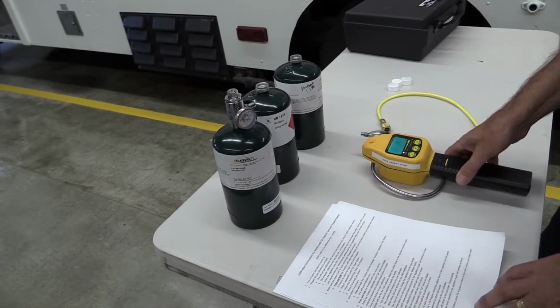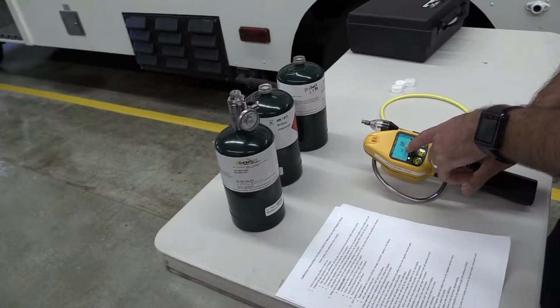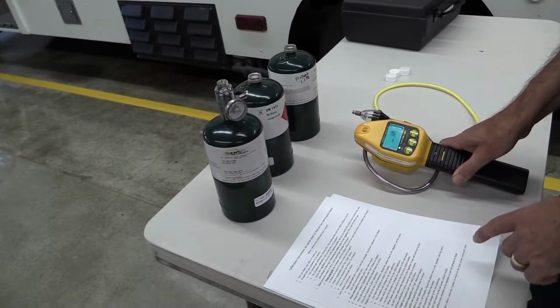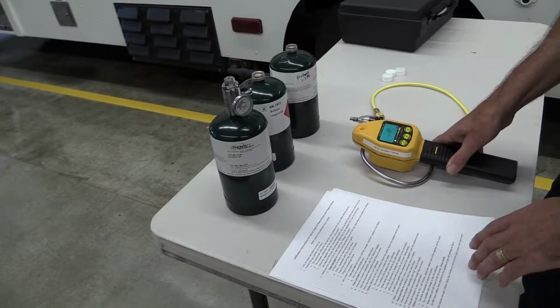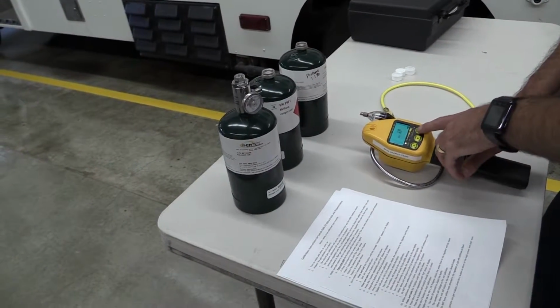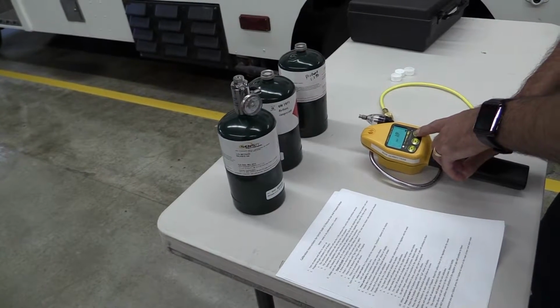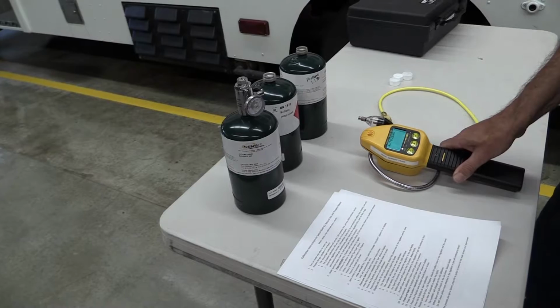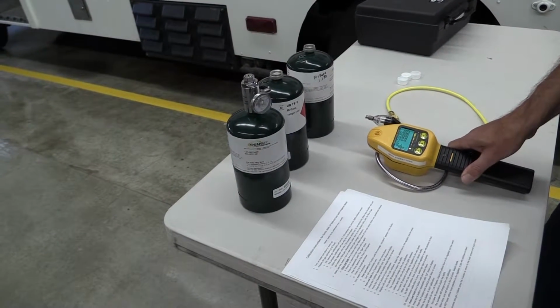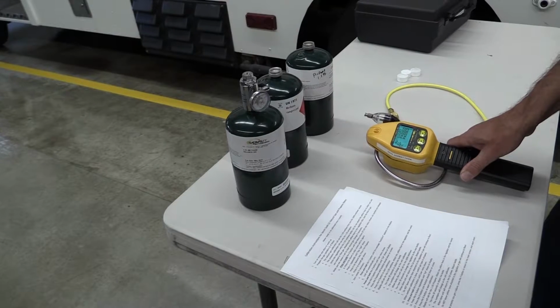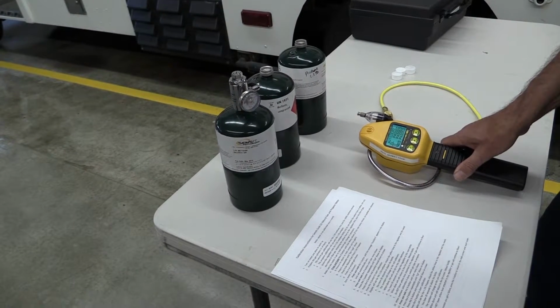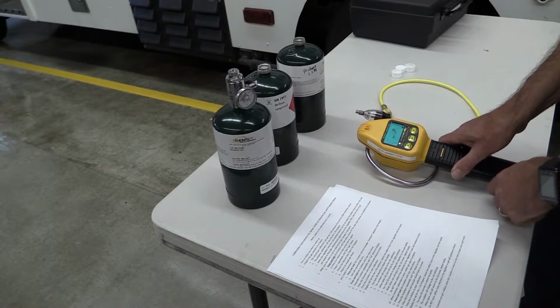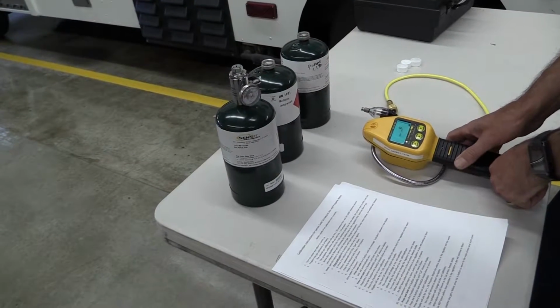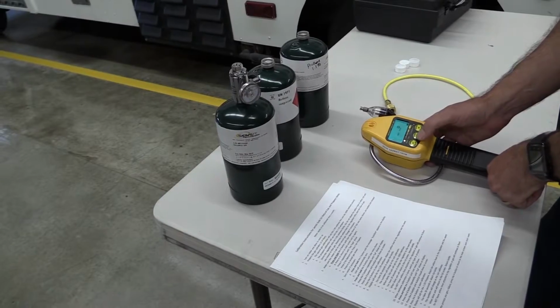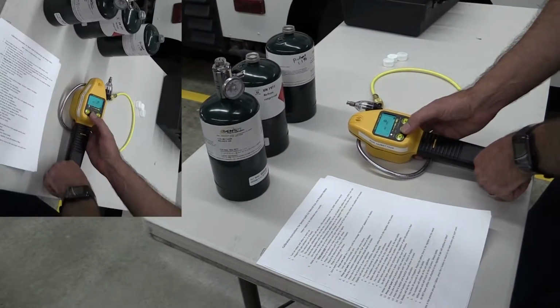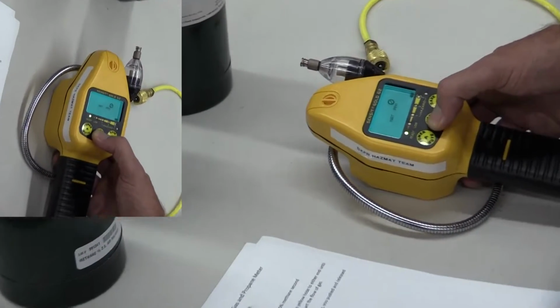Make sure that your meter is set to read natural gas. If it's not, then go ahead and change it back over to natural gas, because that's what we'll start with. Zero the meter if necessary. Once your meter is zeroed and in the correct gas setting, we need to go into the calibration mode. We're going to press and hold the B button until the user menu shows.